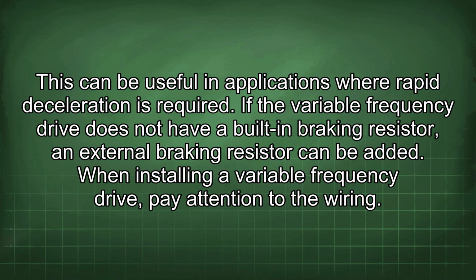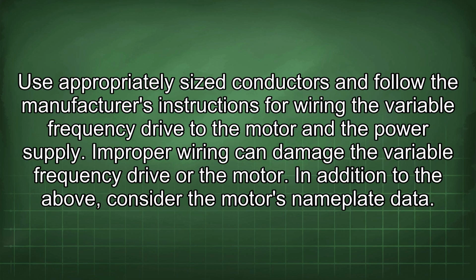When installing a variable frequency drive, pay attention to the wiring. Use appropriately sized conductors and follow the manufacturer's instructions for wiring the variable frequency drive to the motor and the power supply. Improper wiring can damage the variable frequency drive or the motor.